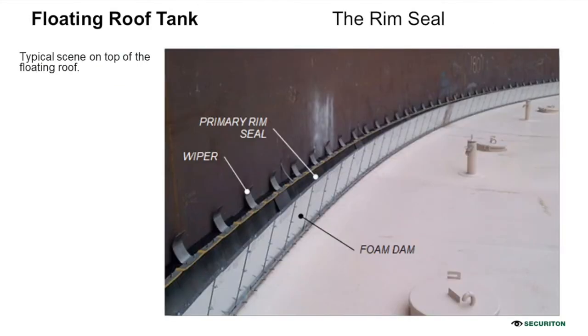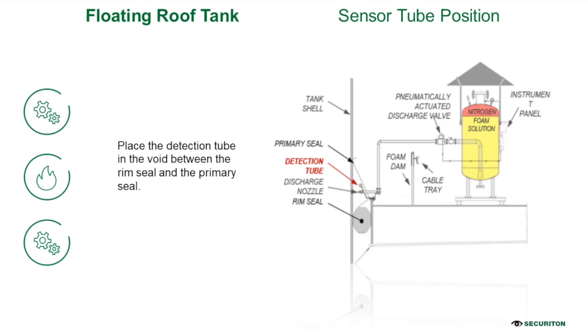Mostly, this will be sent into a nitrogen foam solution which is placed on top of the Rim Seal itself. So the earliest possible signal will be sent towards the pneumatic discharge valve, which in terms of protection is usually connected to a PLC, and that works according to double signal or rate of rise plus maximum alarm, or whichever is possible from our detection side.